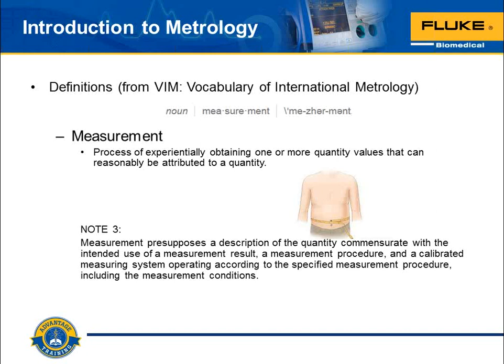Measurement presupposes a description of the quantity commensurate with the intended use of a measurement result, a measurement procedure, and a calibrated measuring system operating according to the specified measurement procedure, including the measurement conditions. So everything needs to be identified, maintained, and controlled throughout this whole measurement. You are really doing science when you're doing measurements in quality assurance testing, in periodic inspections. Anytime you're making a measurement on a medical device, that measurement needs to be reliable in terms of what you measure and what somebody else measures for the same parameter.